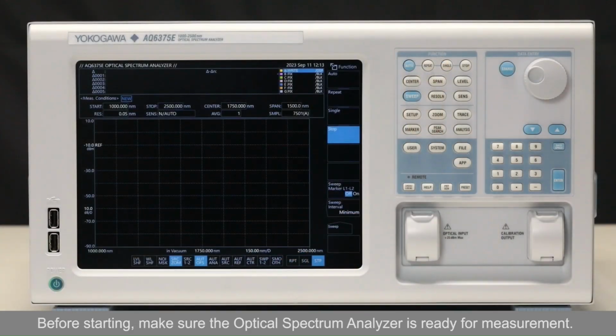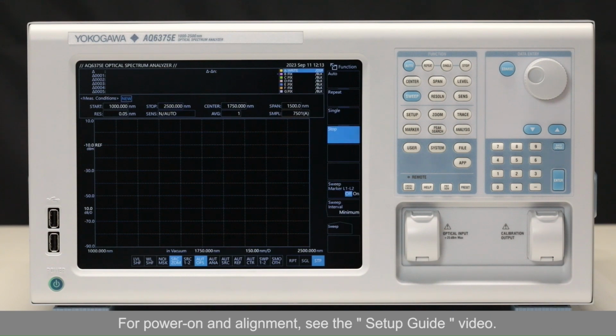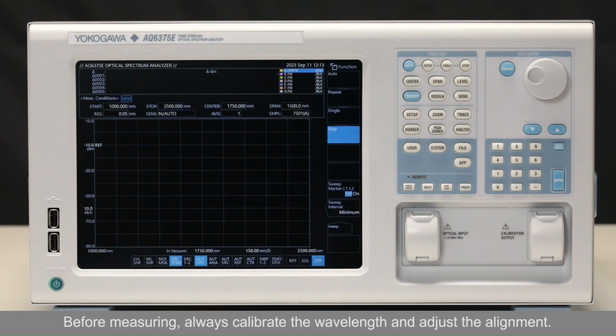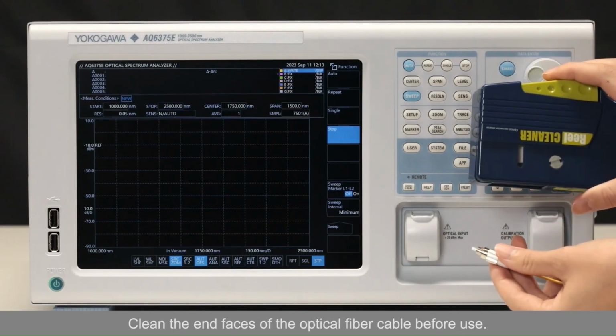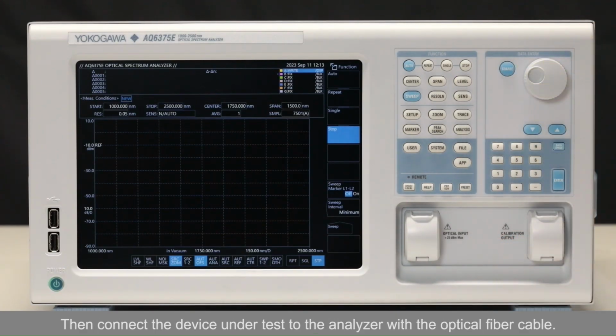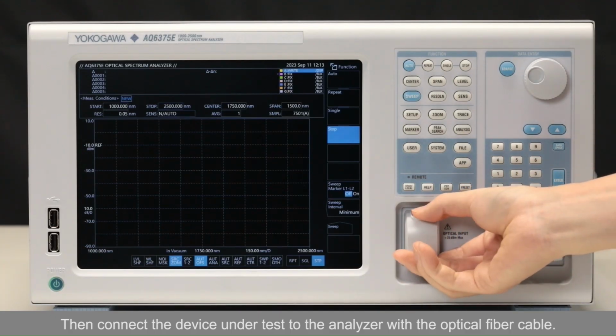Before starting, ensure the optical spectrum analyzer is ready. For installation and alignment, see the previous video. Before measuring, always calibrate the wavelength and adjust the alignment. Clean the end faces of the optical fiber cable before use. Then connect the device under test to the analyzer with the optical fiber cable.